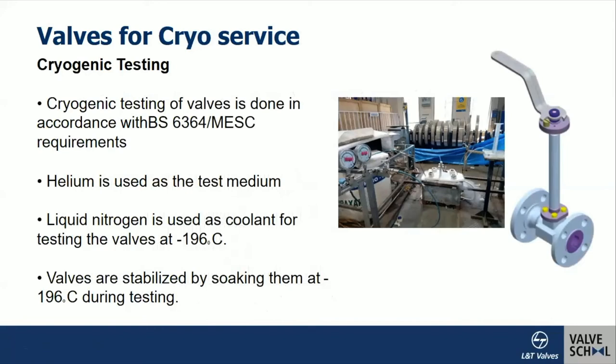Valves for cryogenic service operate at sub-zero temperatures for applications such as liquefied natural gas, liquid oxygen, liquid ammonia, ethane, and ethylene. The relevant standards are BS 6364 and the latest ISO standards for cryogenic valve design and testing. Valves are taken down to minus 196°C using liquid nitrogen as coolant, and helium is used as the test medium for leakage testing.